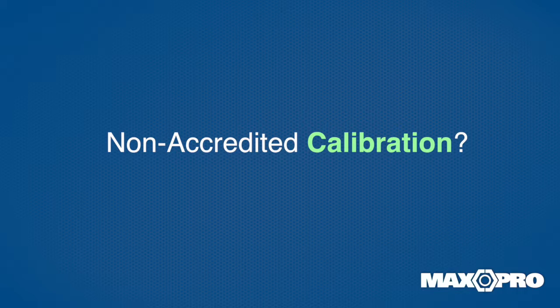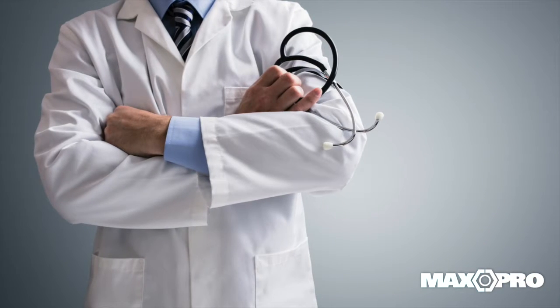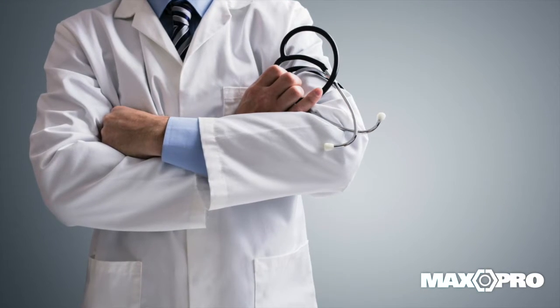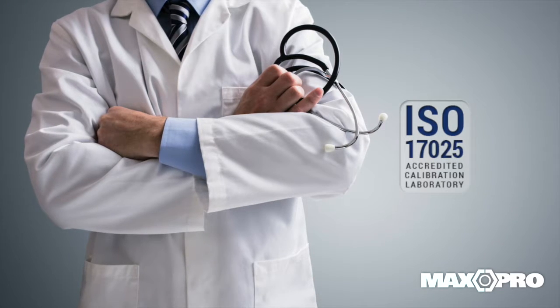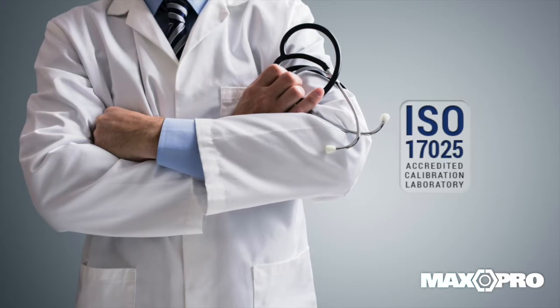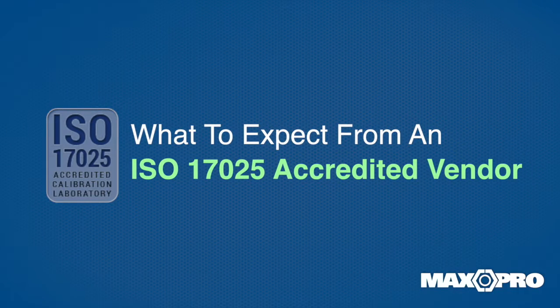Calibration is more than someone putting your torque wrench in a transducer and saying that the numbers pass. A rash of companies are currently calibrating torque tools with no quality system in place. We can equate this to going to a doctor without a medical license. ISO 17025 companies offer a quality assurance program to their customers. Now that we know the consequences of improper calibration or no calibration at all, let's go over the benefits of using an ISO 17025 accredited calibration vendor.